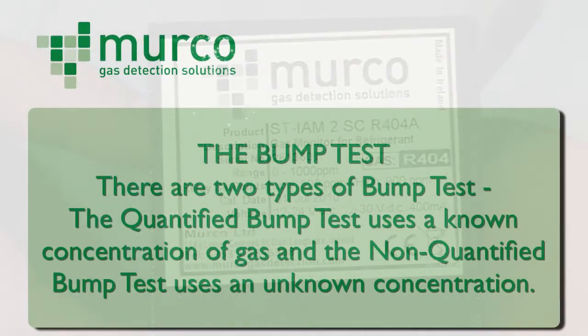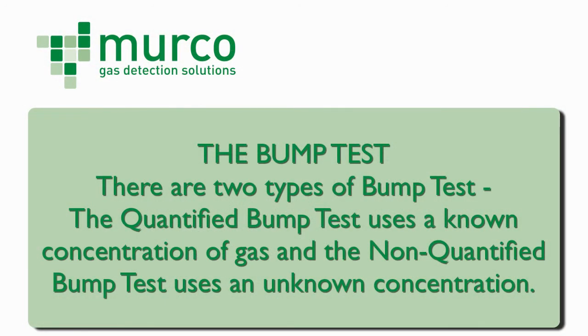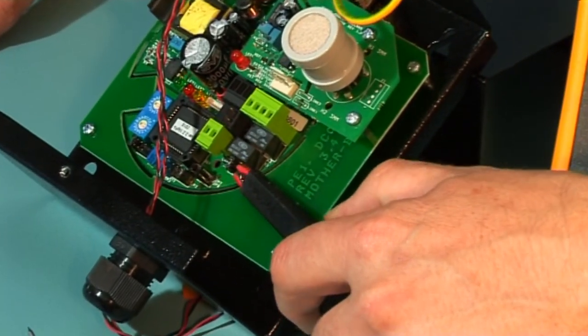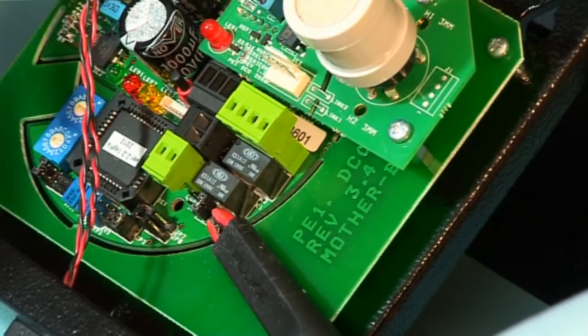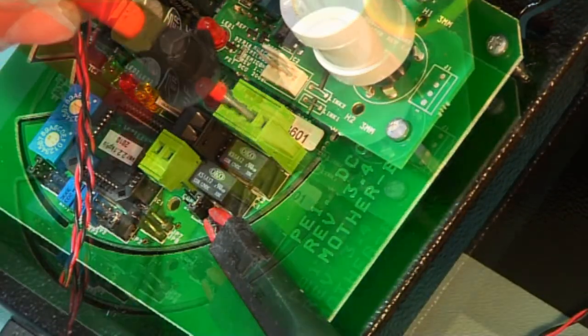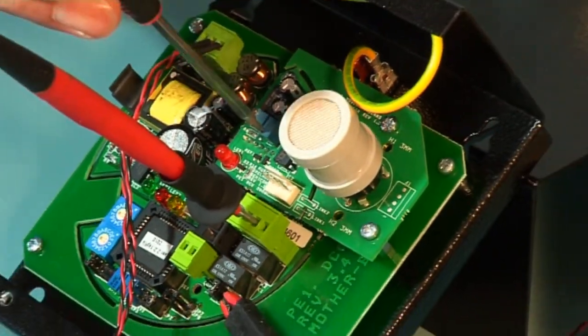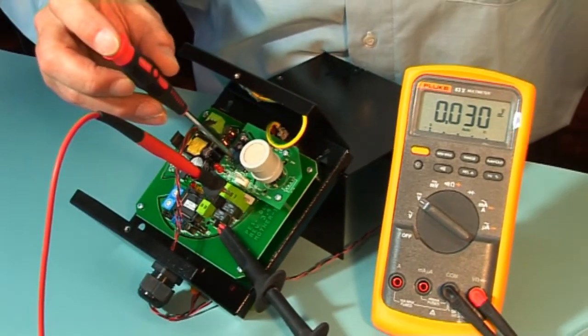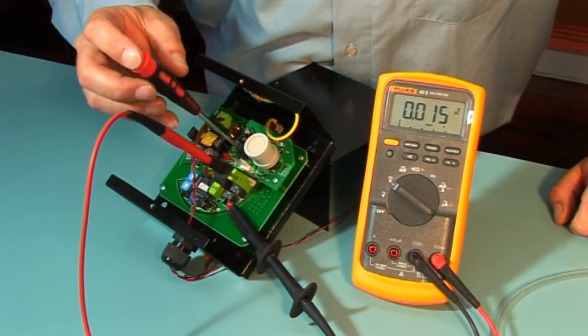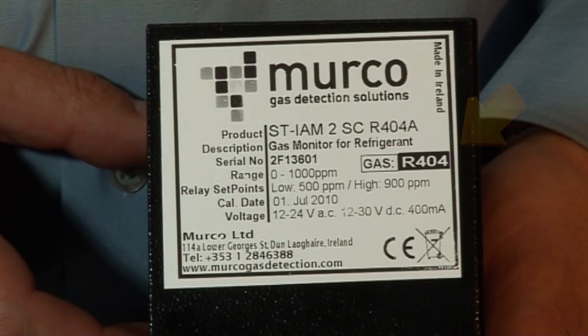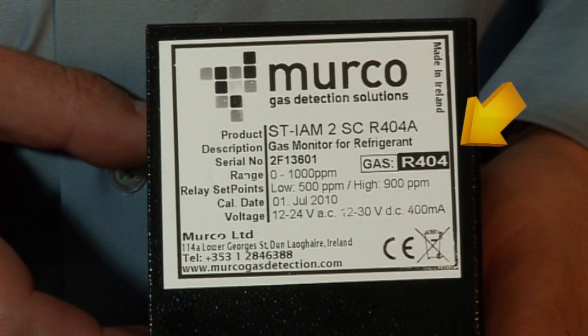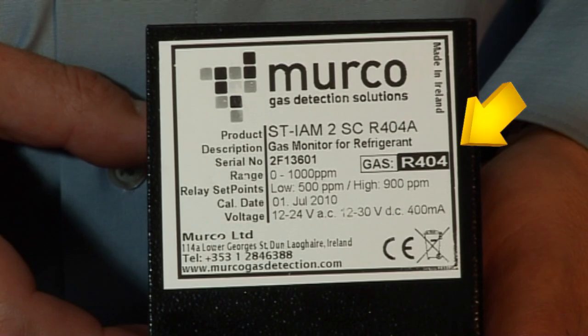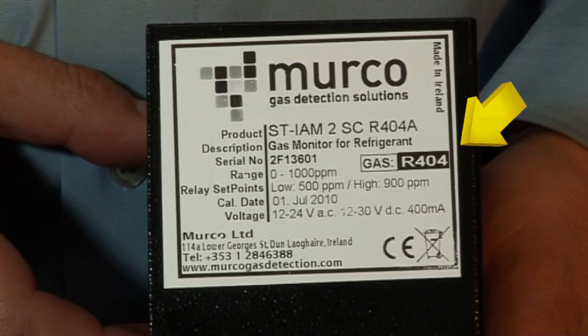There are 2 types of bump test. The quantified bump test uses a known concentration of gas and the non-quantified bump test uses an unknown concentration. Connect the voltmeter between TP0 and pin 3 on the CON3 and adjust RV2 to 0 volts in clean air. Once the sensor starts to see gas, this voltage should increase. For a quantified test, you need to use a calibration cylinder of the target gas at the concentration as on the rating label or higher.